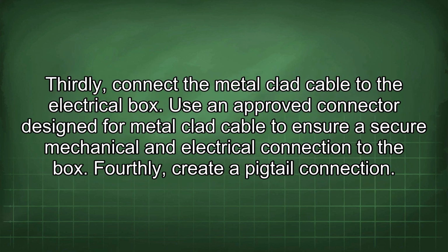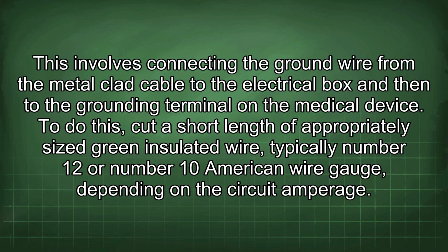Thirdly, connect the metal-clad cable to the electrical box. Use an approved connector designed for metal-clad cable to ensure a secure mechanical and electrical connection to the box. Fourthly, create a pigtail connection. This involves connecting the ground wire from the metal-clad cable to the electrical box and then to the grounding terminal on the medical device. To do this, cut a short length of appropriately sized green insulated wire, typically number 12 or number 10 American wire gauge, depending on the circuit amperage.